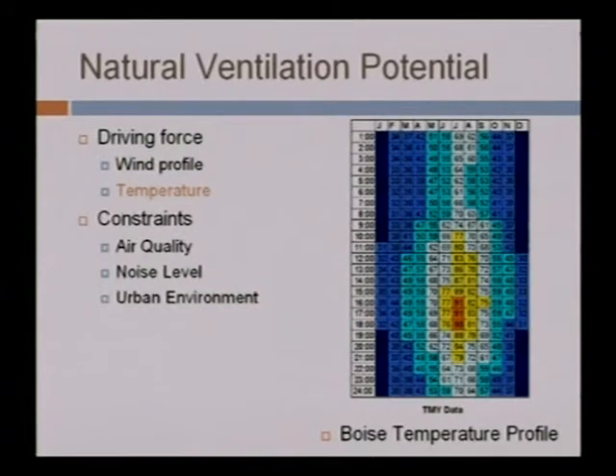But before we make further conclusions, let us look at the temperature profile in Boise based on the TMY data. This is the 12-24 chart, meaning 24 hours and 12 months. I put the temperature in color, with the numbers here. Immediately we can see that in the afternoon hours in June, July, and August, the temperature gets very high. That means in these months and hours, we cannot have free cooling from natural ventilation.